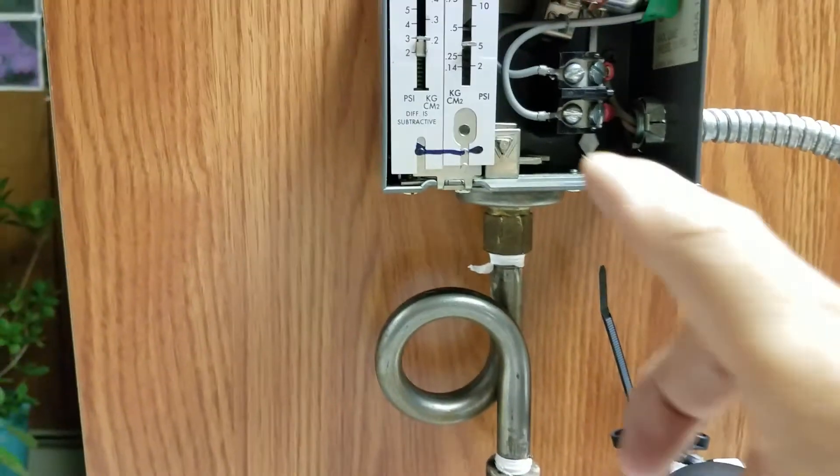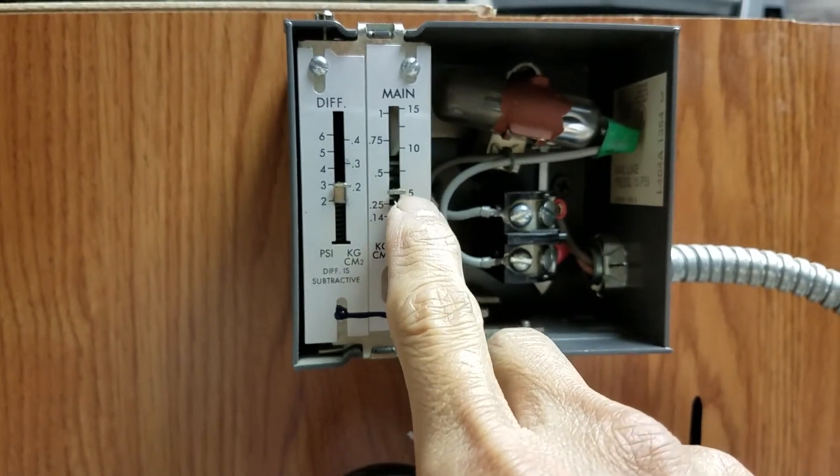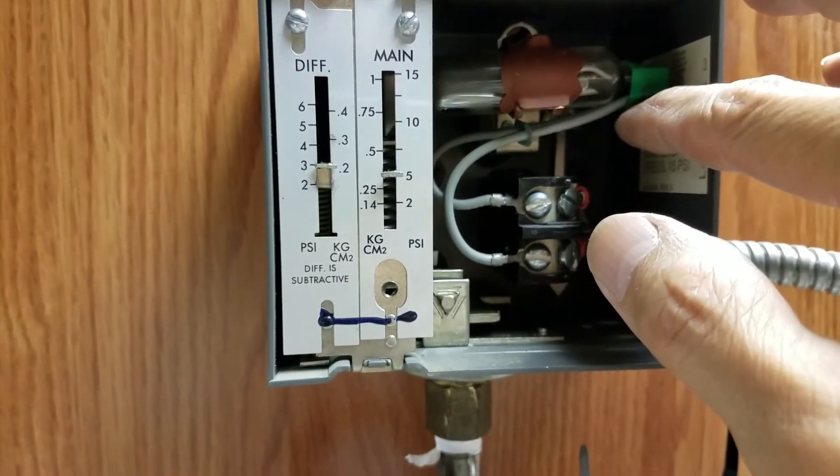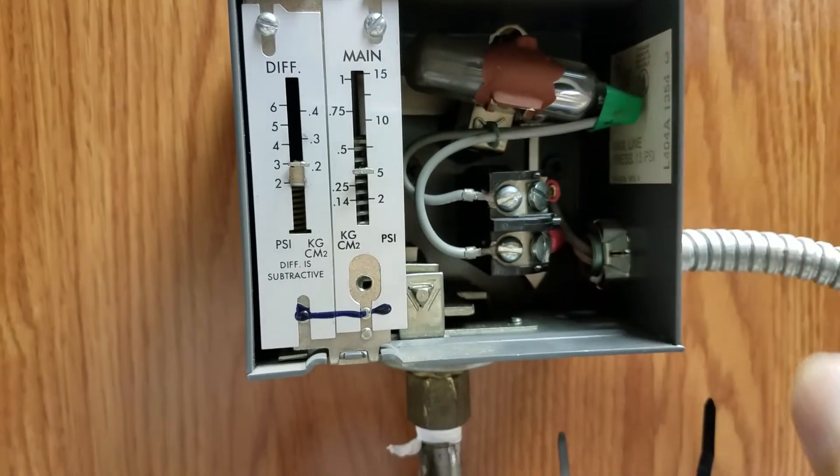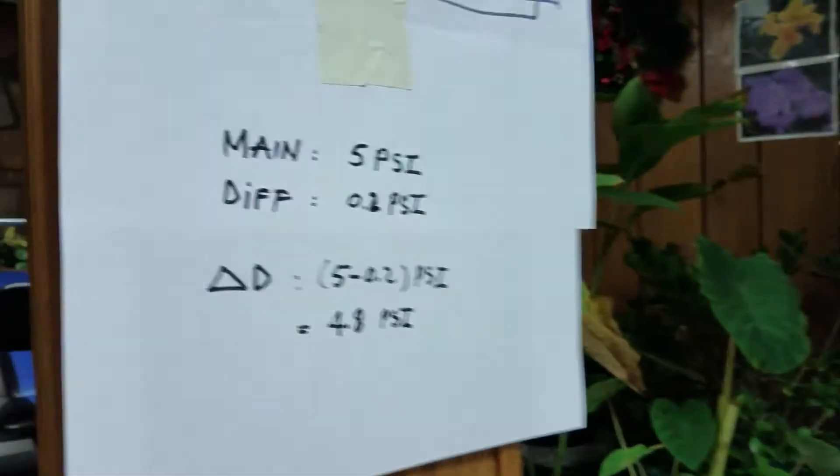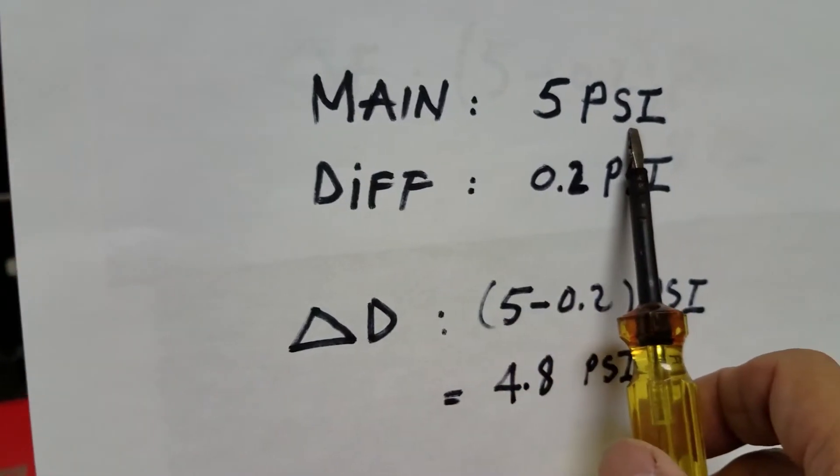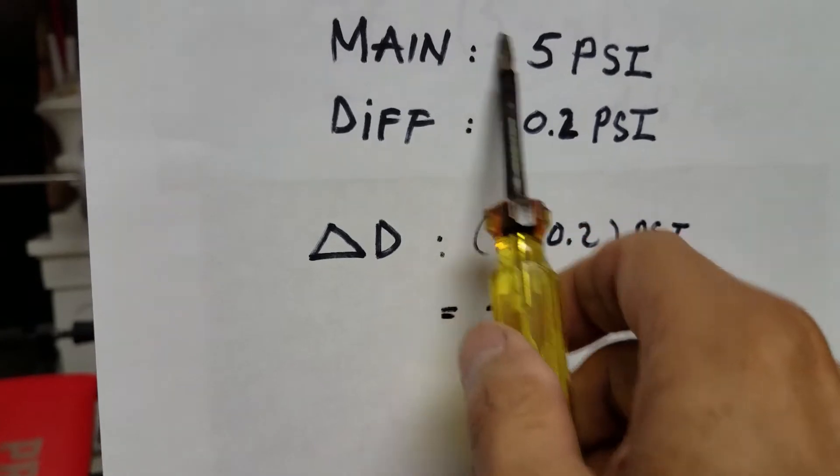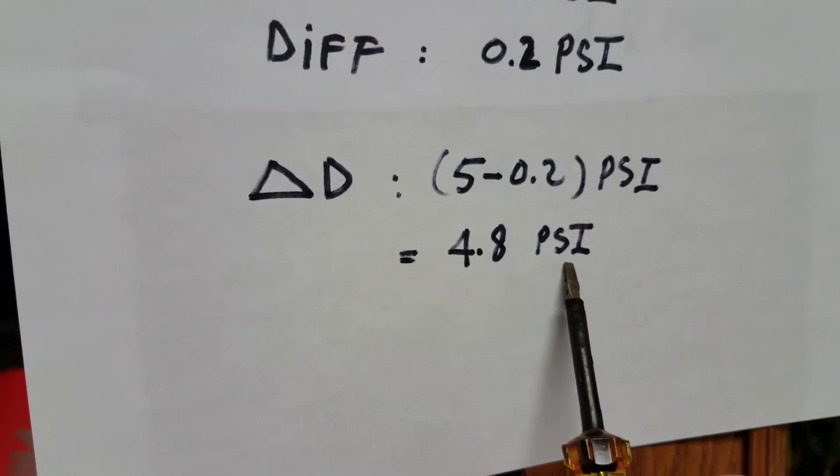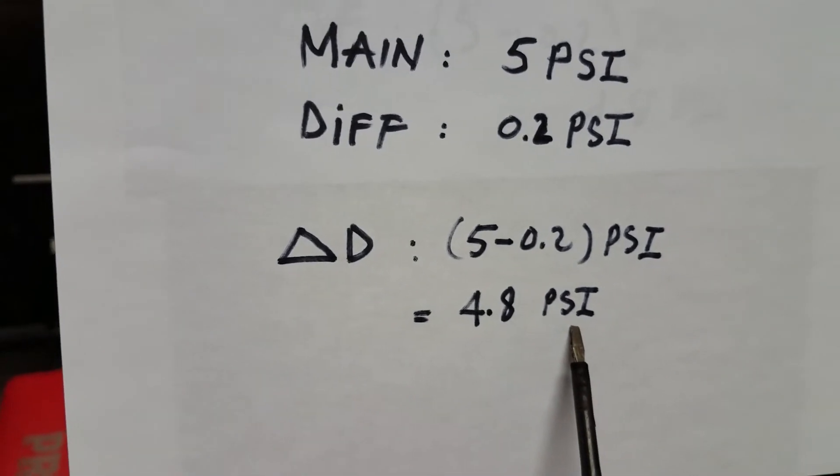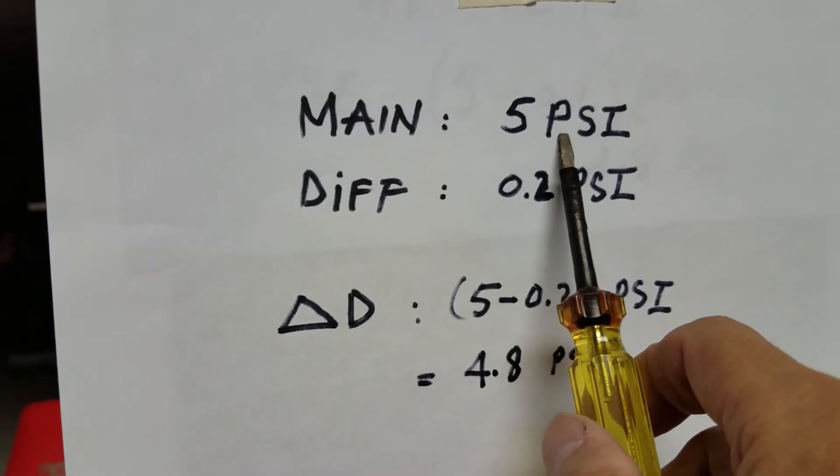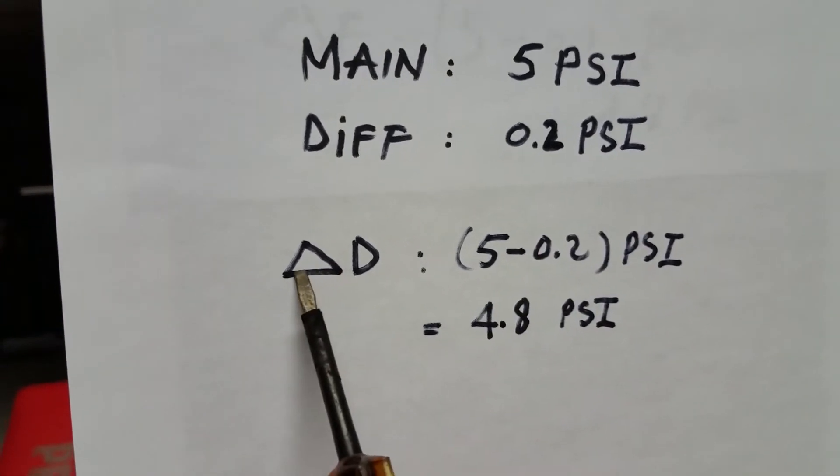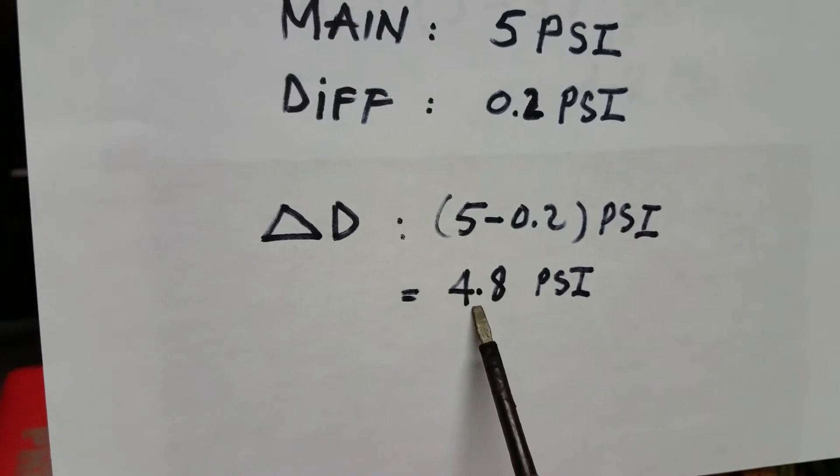When you pump up to 5 psi, contact will open. And when the pressure starts to drop to 4.8 psi, contact will close again. Automatic reset. Right now I'm going to show you on the paper. The main 5 psi. Differential 0.2 psi. If the movement between 5 to reduce to 4.8 psi, the contact will reset. At 5 psi, contact will open. And because you adjust the differential at 0.2 psi, the differential pressure for both, become 4.8 psi contact will reset.